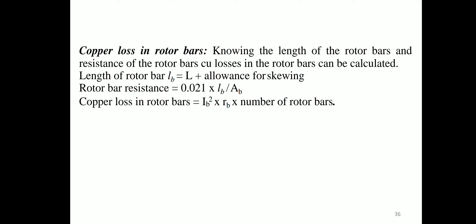Copper loss in rotor bars is calculated knowing the length and resistance of the rotor bars. Length of rotor bar: Lb = L + allowance for skewing. Rotor bar resistance: Rb = 0.021 × Lb / Ab. Copper loss in rotor bars = Ib² × Rb × number of rotor bars.